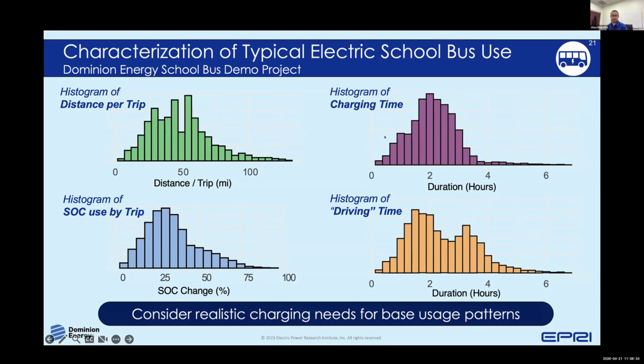The charging duration was usually just a couple of hours, not particularly long. A misconception we encountered is how long it takes to charge from empty to full, but very often you're not doing that. So looking at the realistic discharge on a typical day versus the worst case day is an important consideration, along with the different state-of-charge usage patterns. This relates back to how you size the battery for the buses you need. In our case, most buses used only around 25% of their state of charge, leaving a lot of headroom for grid services or as a safety buffer so you don't have to worry about depleting the last few percent of charge.